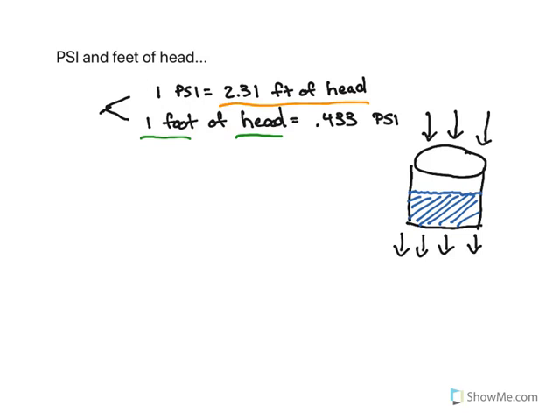So for every pound per square inch equals 2.31 feet of head, or every foot of head equals 0.433 pounds per square inch. These problems that you see are pretty straightforward. For example, let's take a look at a problem like question number one: convert, I'll say as an example, 160 feet of water to pounds per square inch.